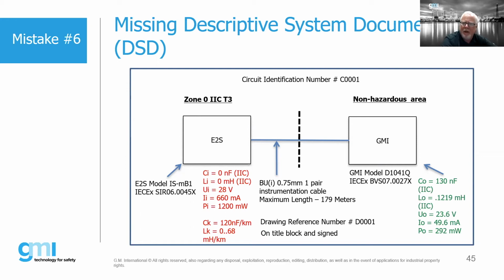But this is really important to make sure that we have this. And we have it from an inspection standpoint because we want to be able to go back and check to make sure that the barrier that was originally installed is the same brand, the same product, and that the field device is the same brand, the same product. And very importantly, we want to make sure that the cable run does not exceed the maximum length. So when we take all that, then we know that this is a safe installation. So this is what is called our DSD, and this is the reason why it's important.